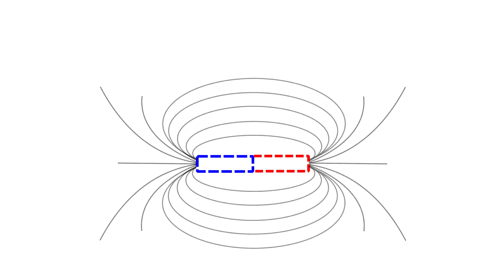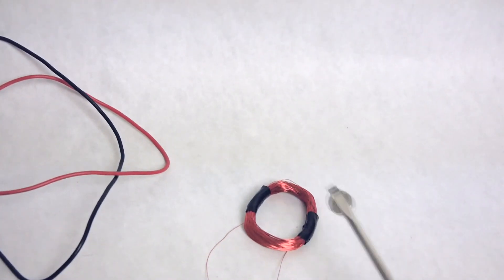A magnetic flow meter relies on Faraday's law of induction, which basically says this: Moving a conductor through a magnetic field will generate an electromotive force, which is proportional to the velocity. Let's break that down just a bit with an example.